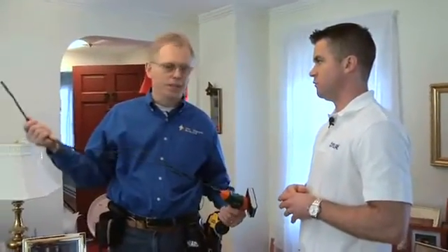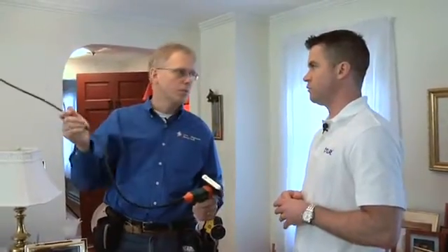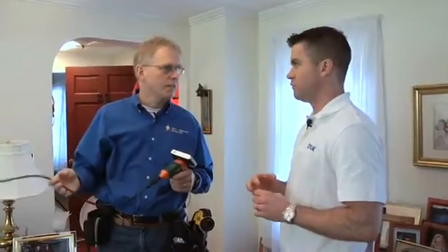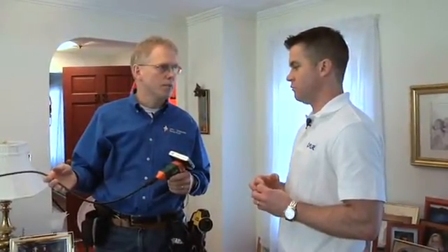Okay, so you actually use this to physically look inside the wall? Yeah. We may have a wall where it looks like there's some issue, but I can't really see exactly what it is. Or if we are looking between the floors, I often use it for that. Is the band joist that's going around the whole exterior of the house insulated? If I can find a way of getting in there with a bore scope and make maybe a small hole like this, then I can totally confirm what they need to do to improve the house.